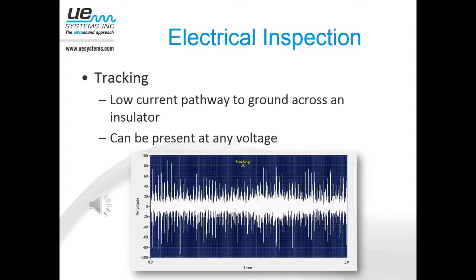That one's probably more difficult to pick out the anomaly, but essentially we look at three things with electrical inspection. We look at how much the amplitude changes, how much it gets louder or softer. We look at how often you have little events, little pops and cracks. You can see a whole bunch of little peaks, which in a time waveform means you had a little mini arc. Then, when they happen, how long do they last? Some of these are fatter than others, so it lasts a little longer as that current travels across a pathway, across an insulator or a bladed connection inside a switchgear cabinet.